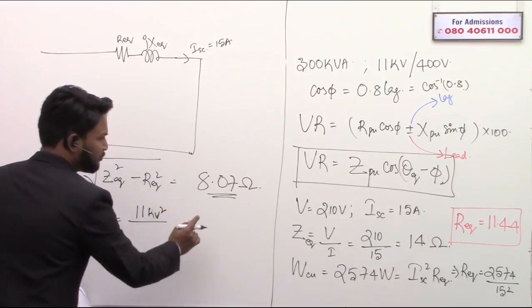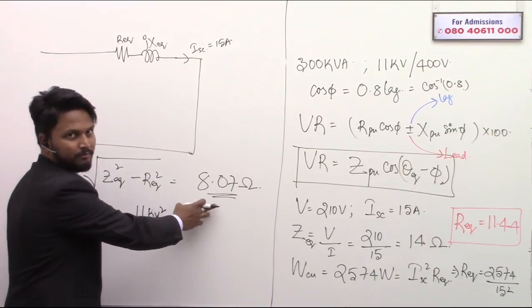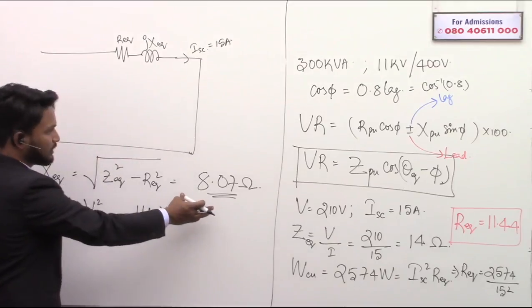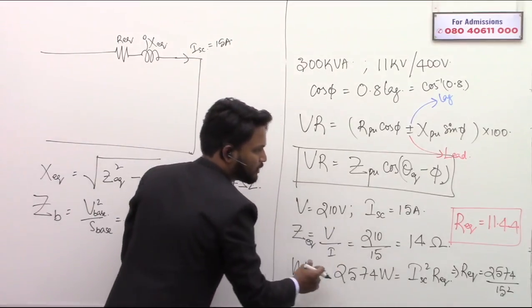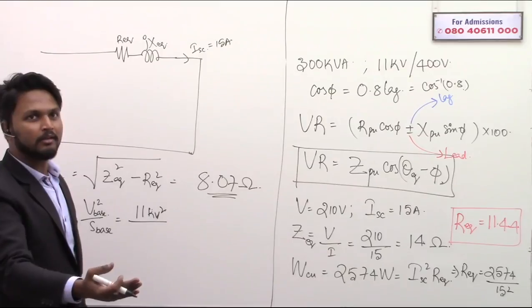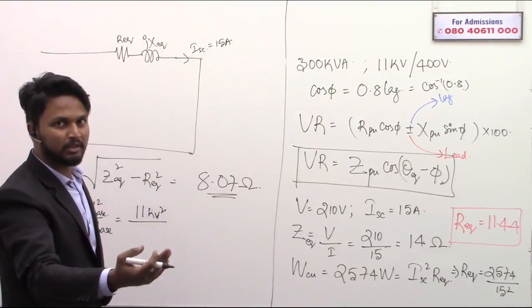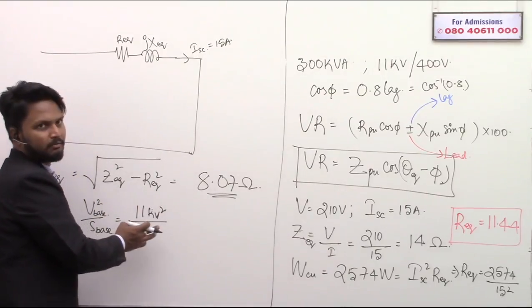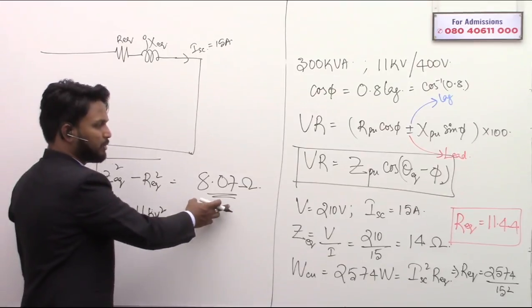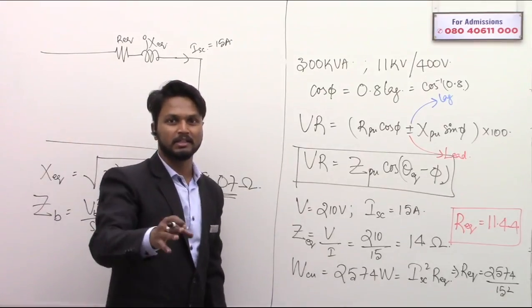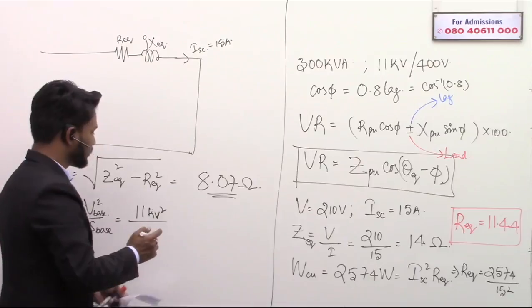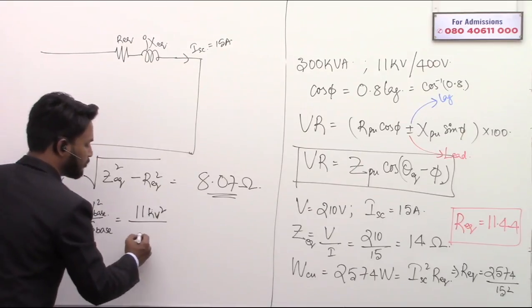Right. If you get impedance on the LV side, and you refer this Z per unit, X per unit and R per unit to the HV side, or to the LV side, you can use the LV voltage. But the impedance you got is the impedance on the HV side, the HV winding of the transformer. Therefore, it is 11 kV squared upon S base.